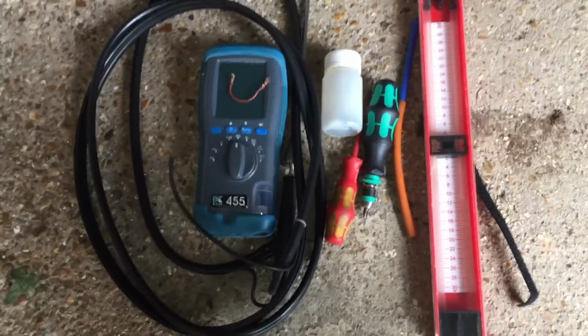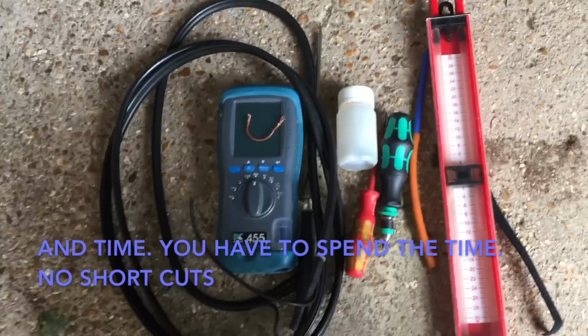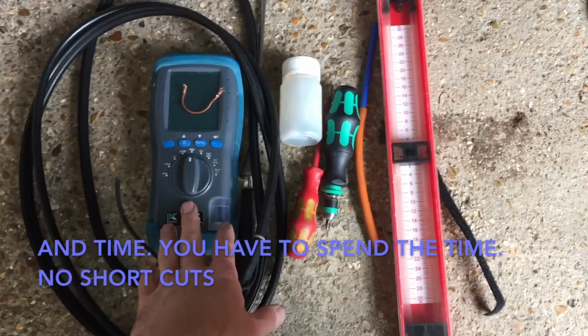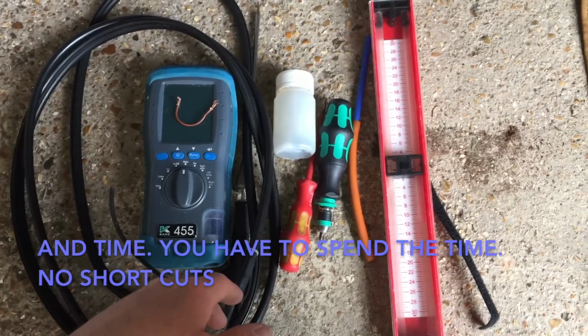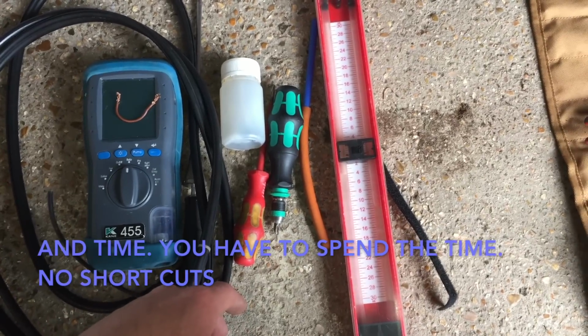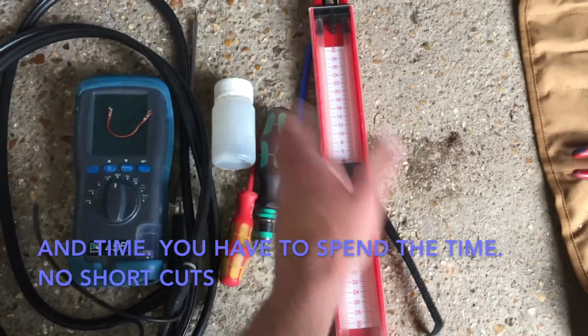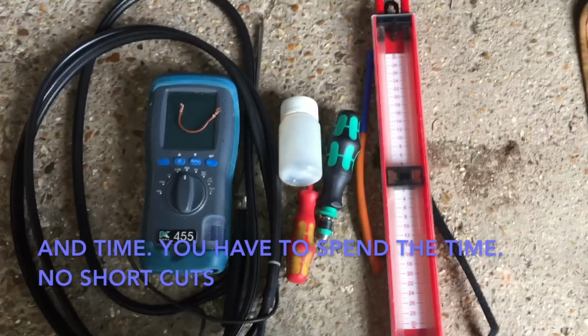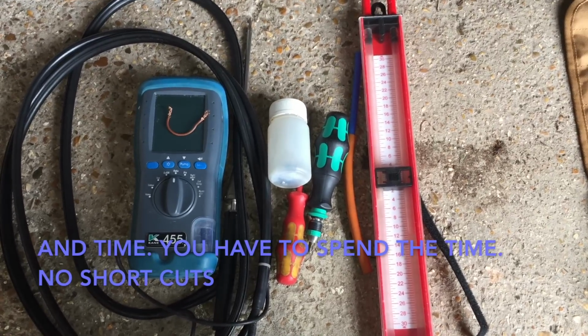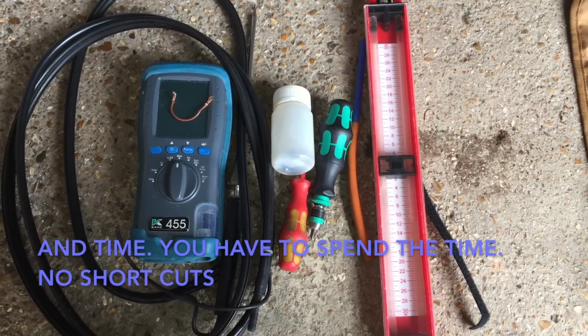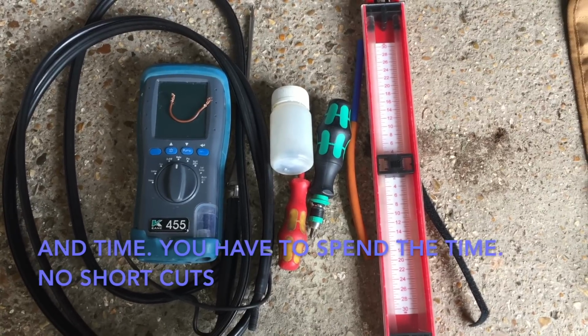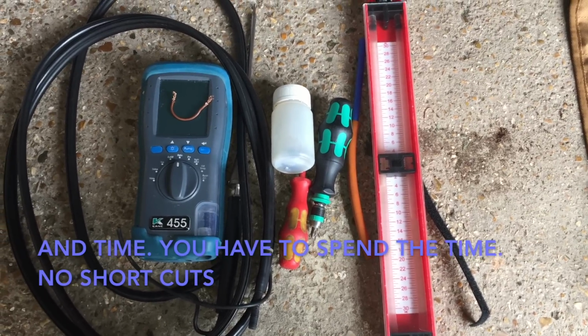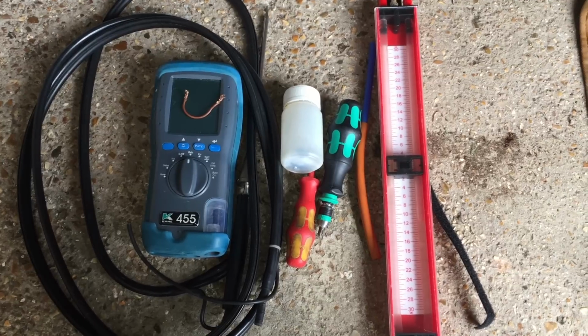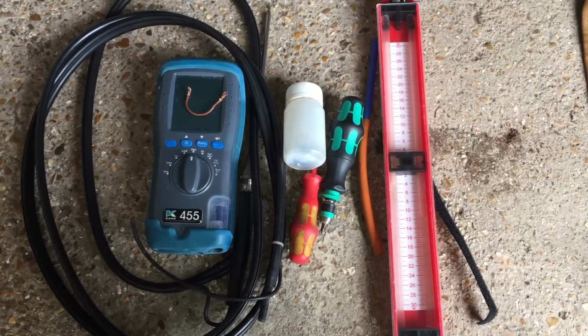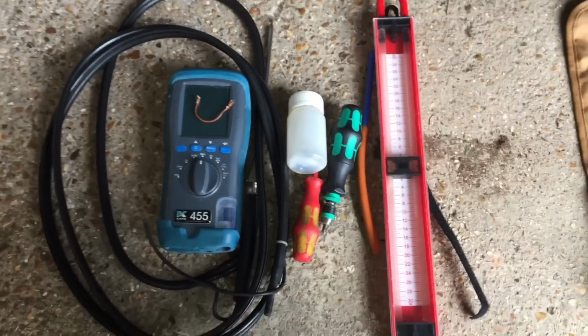Okay, so this is what it took to fix this boiler: a flue gas analyzer, a flat screwdriver, a Phillips screwdriver, the U gauge - I know I used 2, but you could have just used 1 and taken it off and put it back on - and leak detection fluid, and that's it. It wasn't a very involved fault, but engineers, you've got to keep it simple. Engineers aren't keeping it simple, and they're going looking for problems that just aren't there.